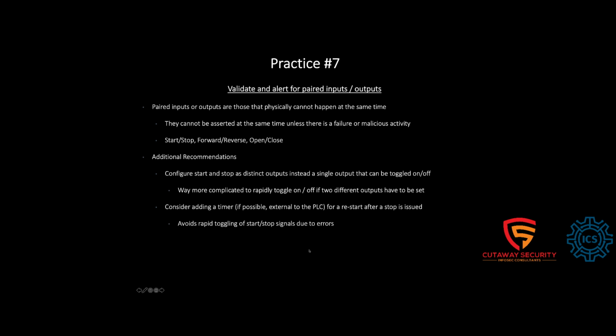And then you can also add a timer outside of the PLC if possible, but also a soft timer for a restart. Again, we're trying to add to this practice: if you have a restart, try to avoid a rapid toggle on the restart by adding one more layer in between, so that an attacker cannot easily just force one bit to 0 and 1 and constantly toggle, like the Aurora attack, where they forced the breaker to open and close rapidly. Maybe this is not a breaker, maybe it is something else, but you're trying to avoid something being turned on and off rapidly.